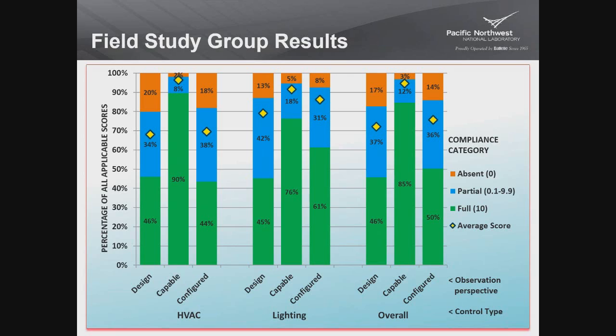And as we've seen before, this is quite a bit lower. HVAC, only 44% of those requirements were set up to operate the way that the code is asking that they are. 18% not at all, and 38% scored somewhere in between with an average score of 7.0. Lighting, a little bit better, 61% fully compliant, perfectly compliant, 8% non-compliant totally, and 31% somewhere in between with an average score here somewhere in the upper 80s. And once again, the overall is just combining the lighting and the HVAC.